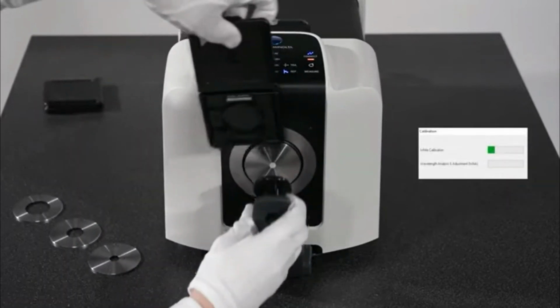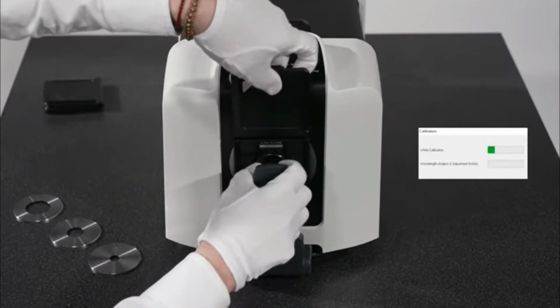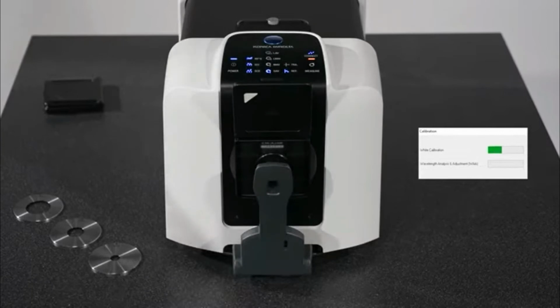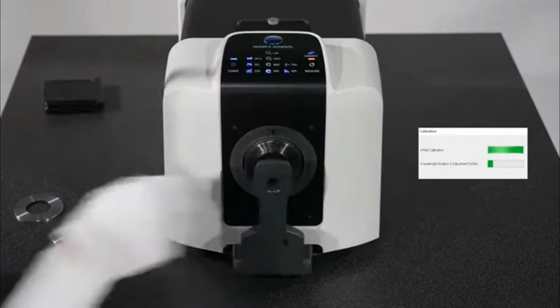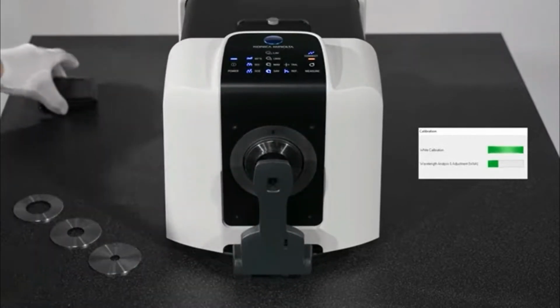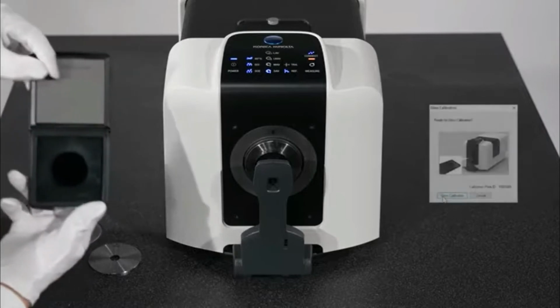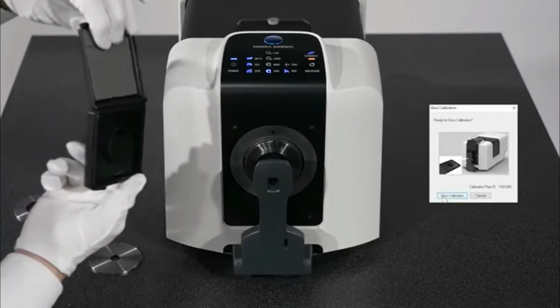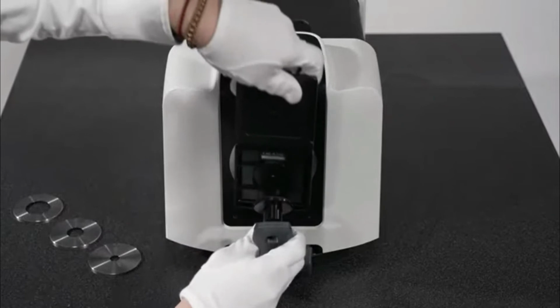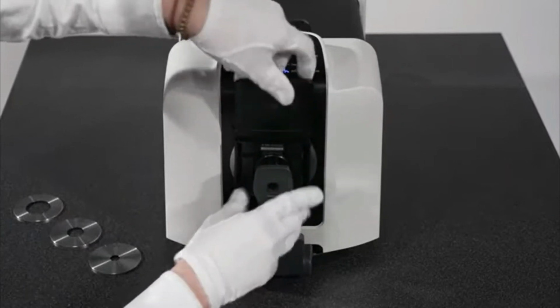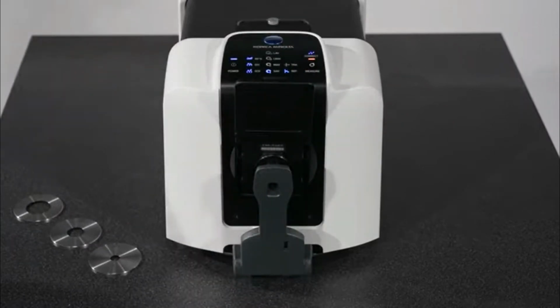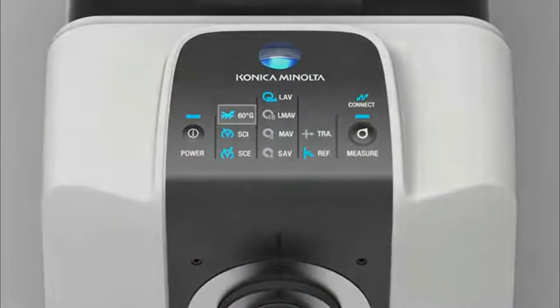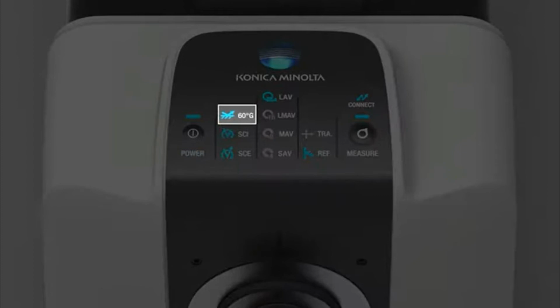Note: if the optional wavelength analysis and adjustment function is activated, there will also be an automatic WAA progress bar after the white calibration is completed, showing that it is going through the analysis and adjustment procedure. When white calibration is finished, follow the prompt for the gloss calibration. Position the gloss standard, then click to start calibration.